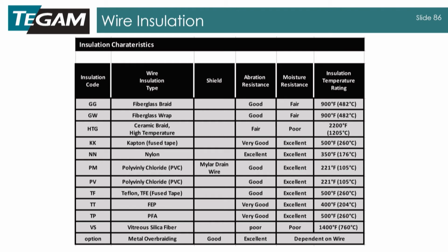All right, next we're going to talk about wire insulation, and this is going to be the actual wire insulation of the cable coming out of the probe. So you're going to want to take this into account in your application. If, let's say, you're mounting this probe somewhere, in, let's say, a 350-degree oven, well, you don't want a PVC insulation because it only goes up to 221. You would want something like maybe a Kapton insulation that goes up to 500 degrees F, because the last thing you want is melting wires in your oven while you're measuring temperature. But this is just another thing to take into consideration. The insulation of your cabling, if it's going to be in the environment that you're measuring, needs to be rated for the environment that you're measuring.